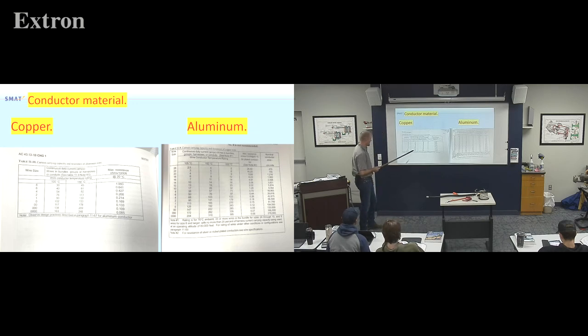Just stop a second because I'm looking at the chart. 105, 150. Good. My dyslexia kicked in. I'm like, it's the same number. So we'll pick 105 degrees Celsius with our aluminum wire. And we'll go 6 gauge, 105 degrees Celsius. And in the very most basic general terms, it's essentially saying that aluminum wire can carry 40 amps. So that's the most basic general terms, and we're going to cover why I say that in a minute.